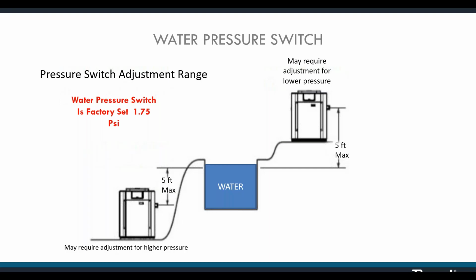If you're installing 5 or more feet below the water surface, you'll need to install either a higher rated pressure switch, which we do have available from Raypak, or a flow switch. We do offer a flow switch as well. There are a number of them on the market. Raypak has one. If you are 5 feet above the surface, only the flow switch will work. Let me tell you why that is. Let me grab my little laser pointer here.